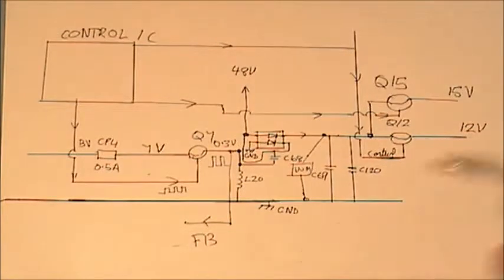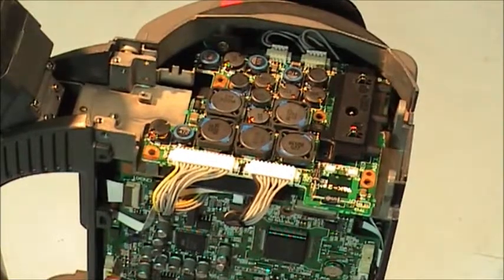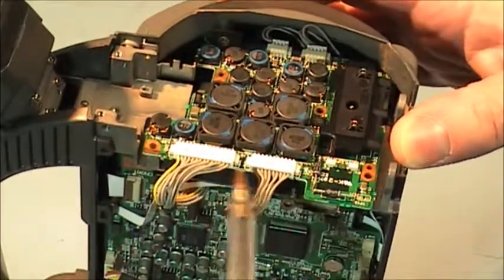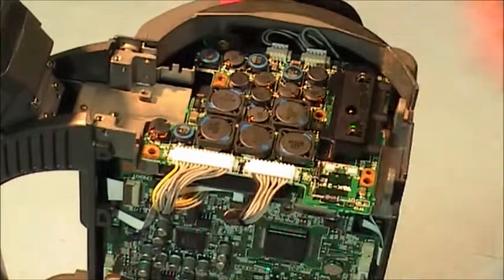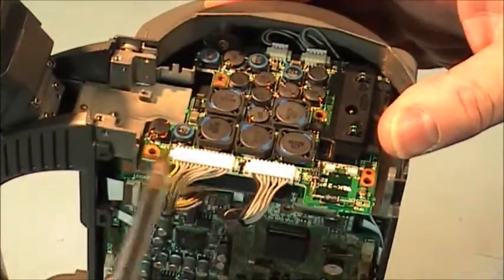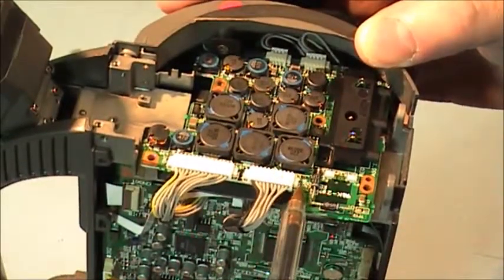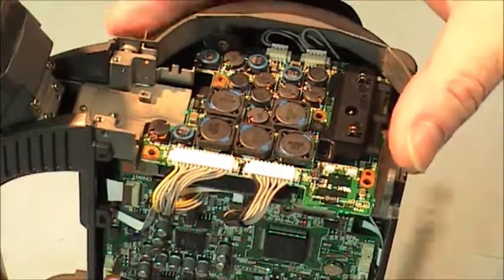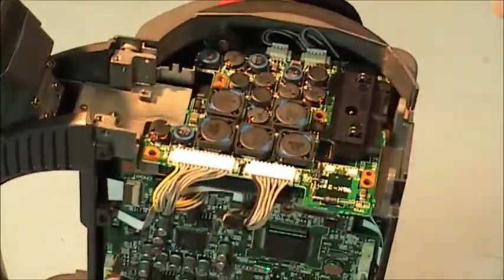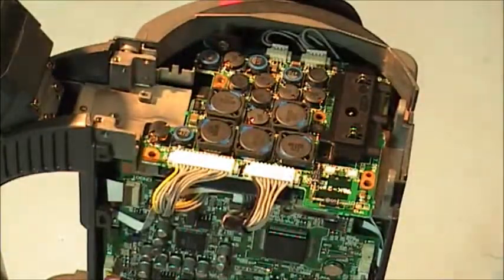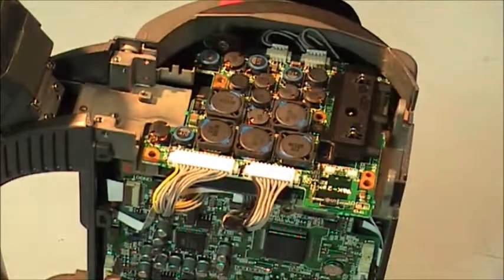Okay, I'm going to just show you the connectors on the power supply. These are the two connectors on the power supply that I'm talking about. This larger connector here is CN7 and this is CN6. Your pin 1 starts at the top on both connectors. This is pin 1, this is pin 1 and this is pin 14, and this is pin 1 and down here we've got pin 10. And you can measure them easily. What I done was I disconnected my on off button and connected back up my panel just to temporarily get it working so I can do a few voltage checks.